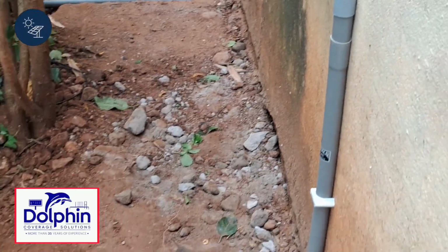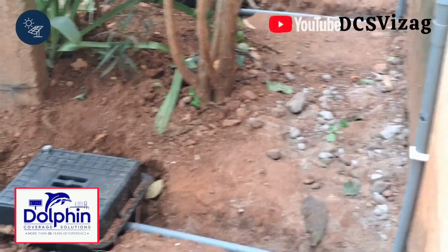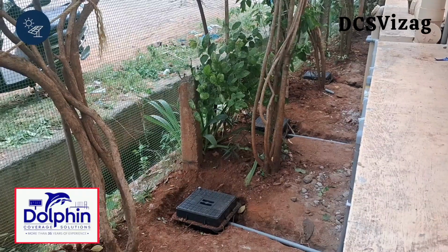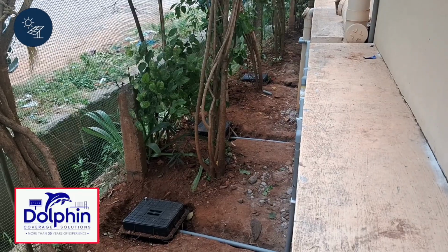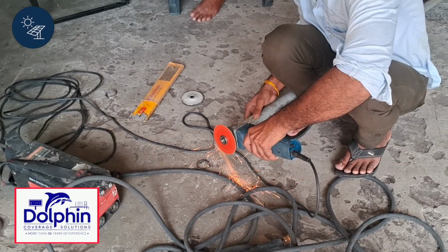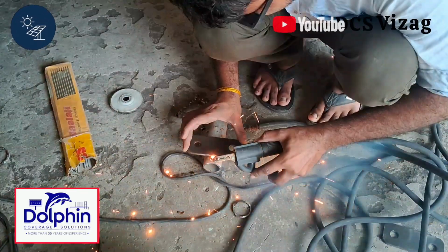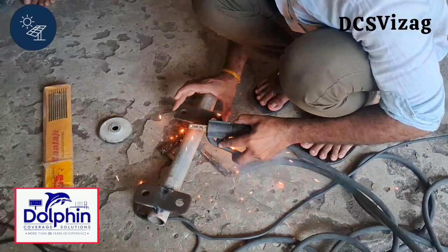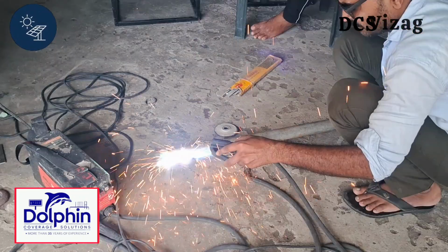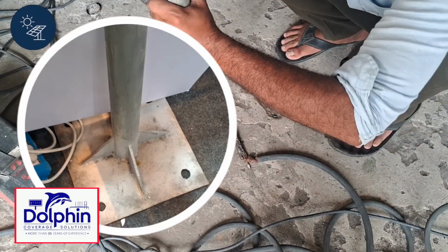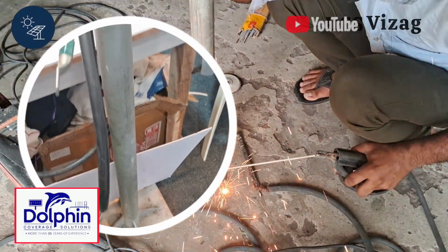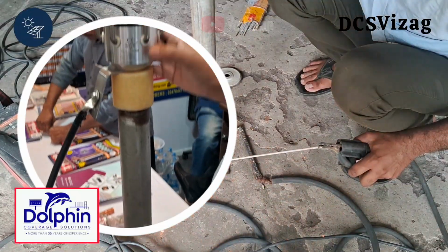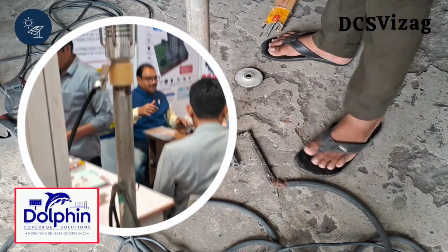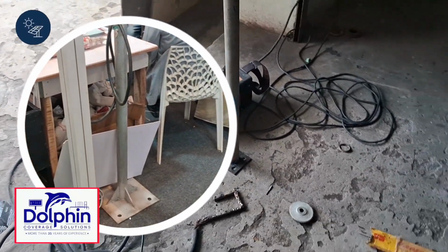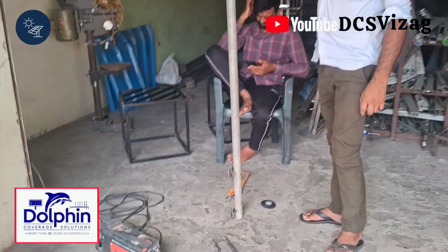system and lightning risk. The grounding cable for PV modules should have a minimum cross sectional area of 6 square mm if the cable length is less than 30 meters, and 10 square mm if more than 30 meters. The grounding cable for PV panels should have a minimum cross sectional area of 6 square mm if the cable length is less than 30 meters, and 10 square mm for 30 meters and above. Target earth resistance. In India, the recommended earth resistance for solar installation is generally less than 5 ohms. For lightning arrestor, it's typically less than 10 ohms.